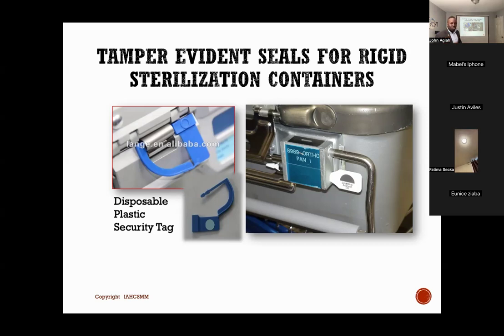Then when this gets to the OR, and the OR breaks this down, they validate the external indicator color change, because before they open the trays, they have to check to make sure the color change outside is intact. The external indicator color has changed. And then they will check what is inside of the trays. That is the most important. The operating room will double check what is inside to make sure that it has changed color. If not, it doesn't matter what the external indicator says.